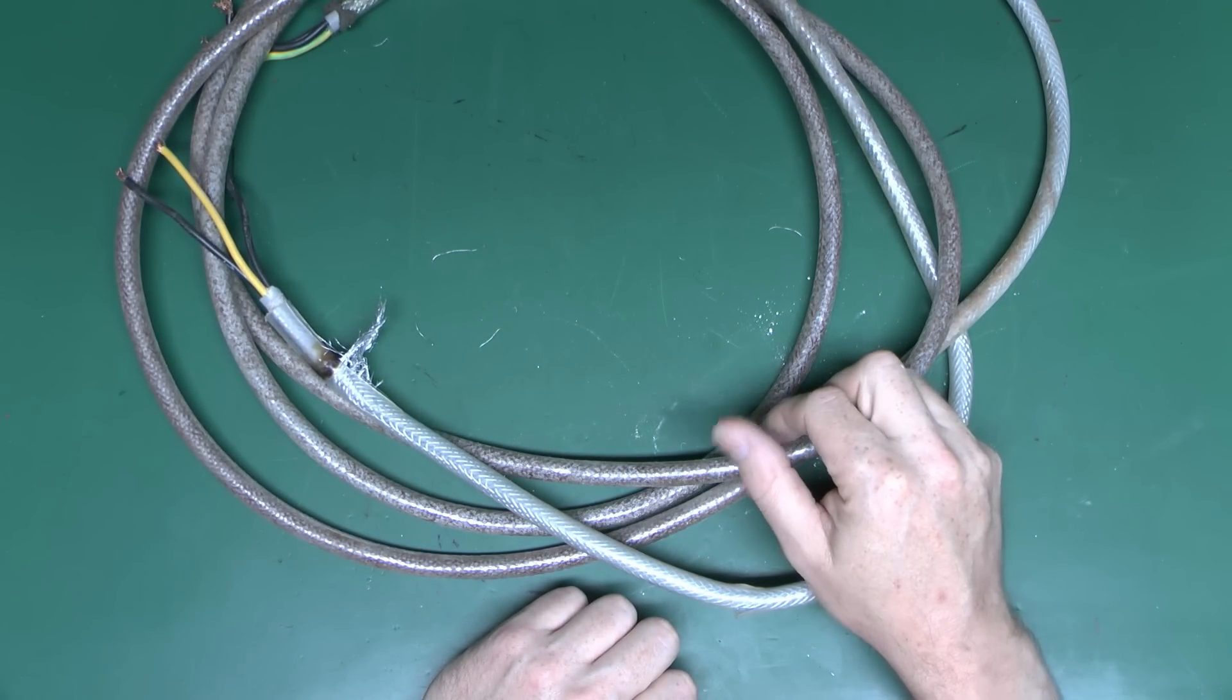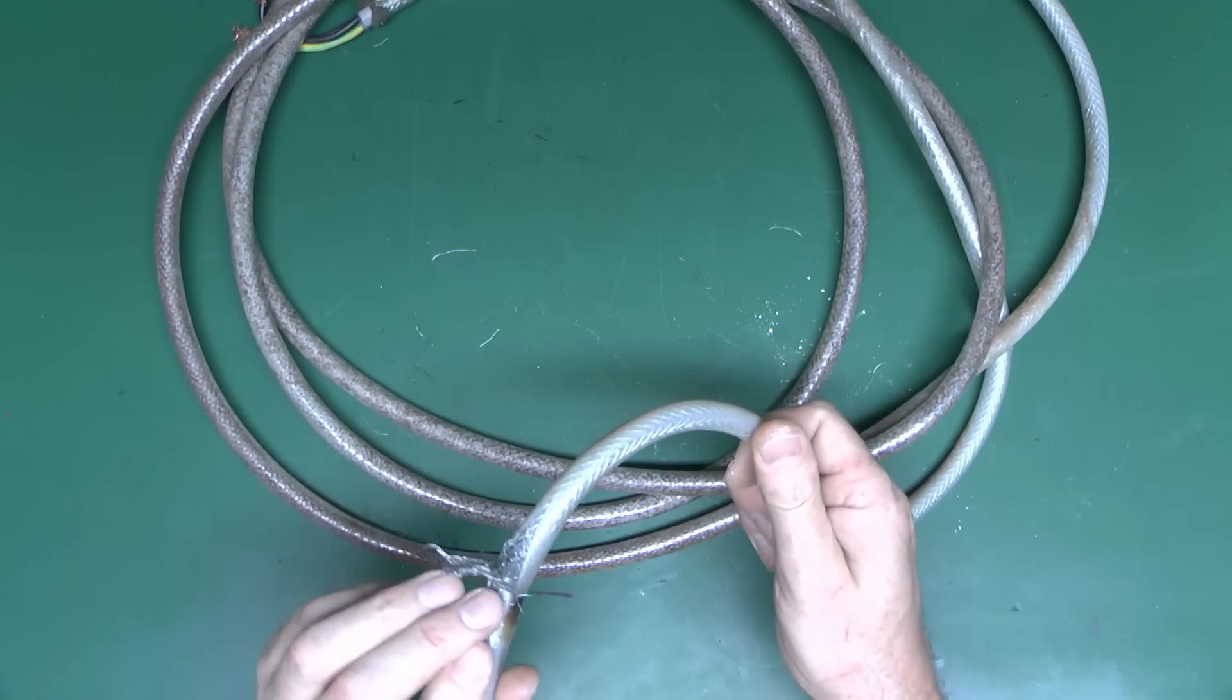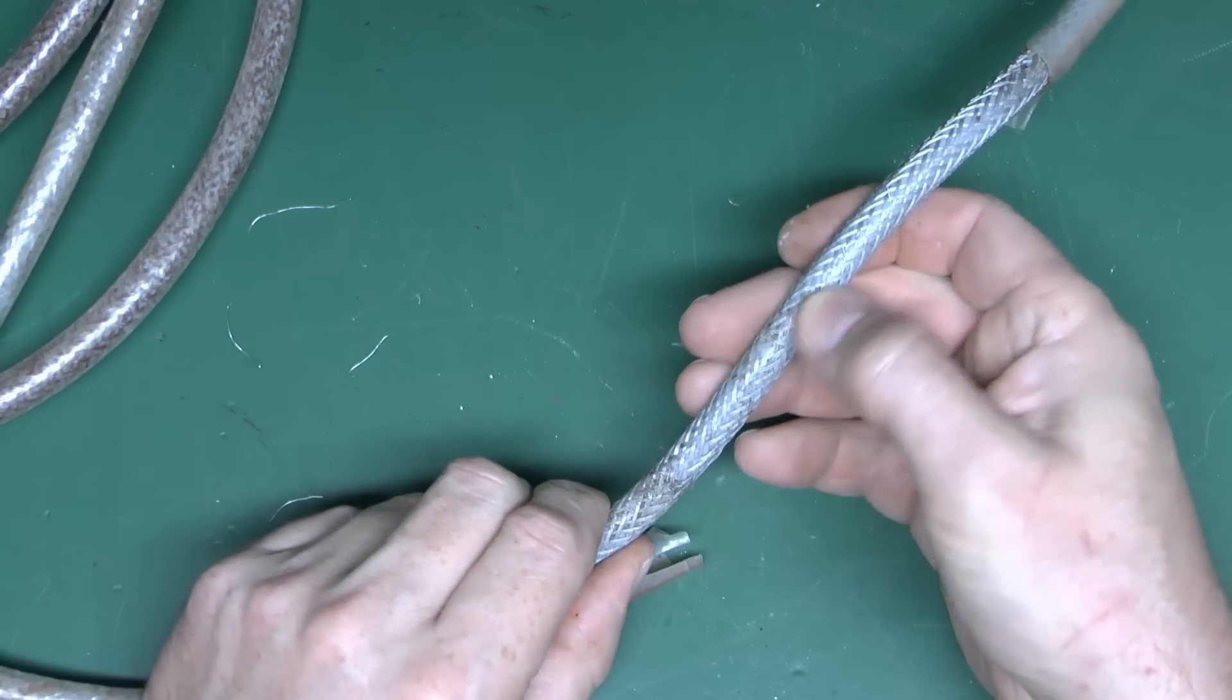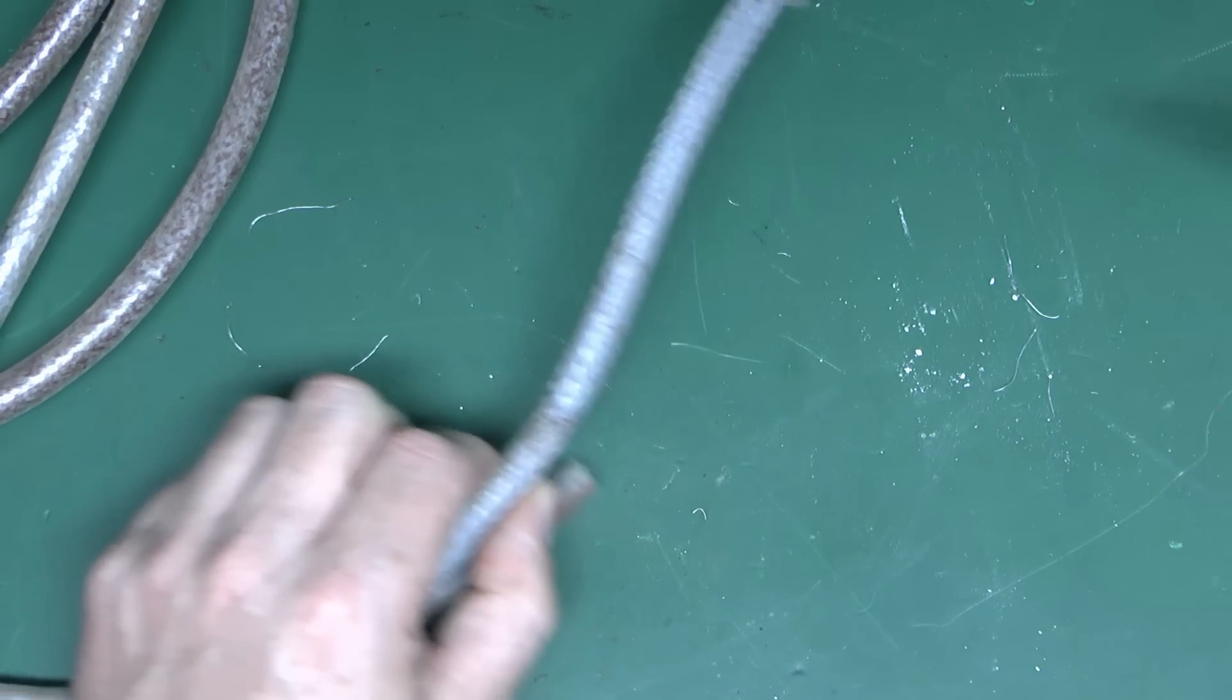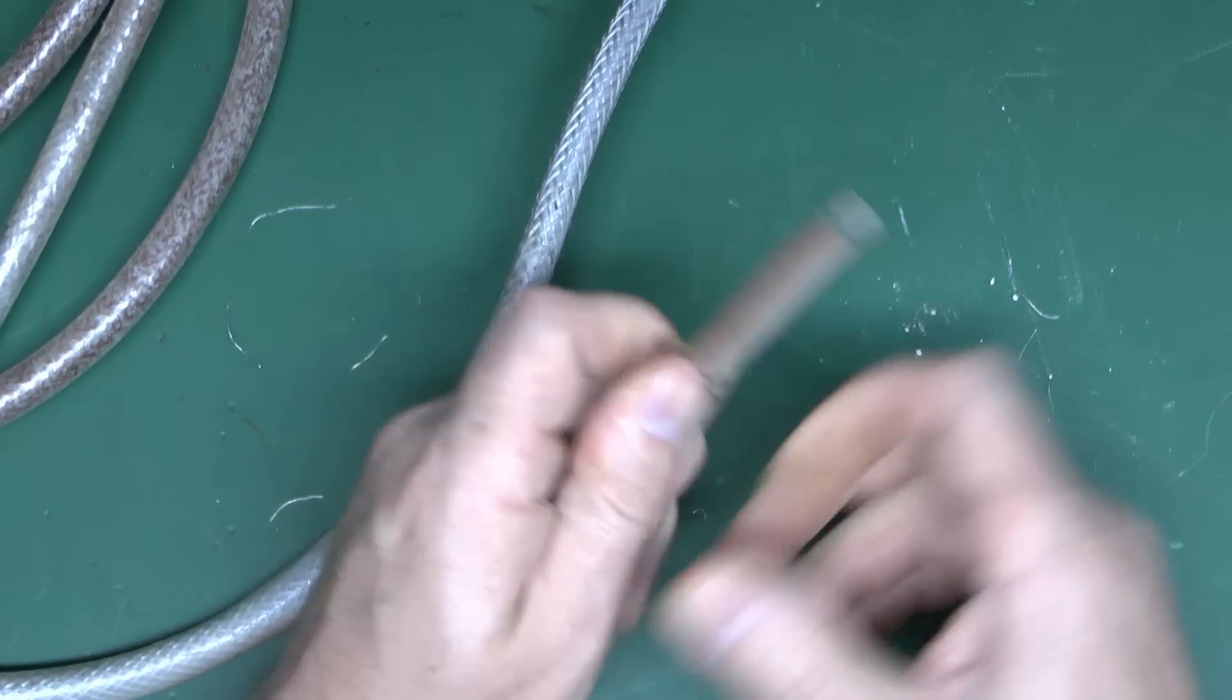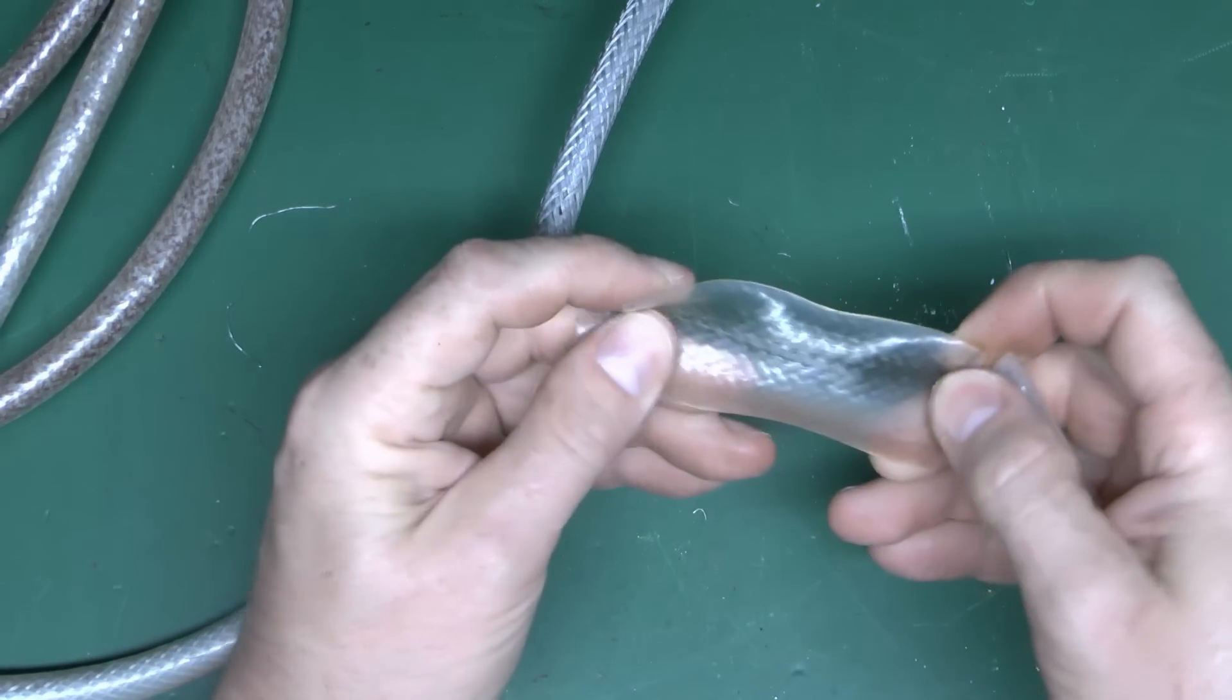Further investigation if it was in reasonable condition. You might want to find out the actual specifications of it, because you can't just go and look up generic SY cable and say all is well. You really need to know who actually made it, and get the specific details of that exact one. You can see here underneath this is reasonably intact, but it's already starting to corrode here where the exposed braid was. And this has gone rather brittle at this point where the moisture and things have obviously got in and the sun has damaged the outer covering.